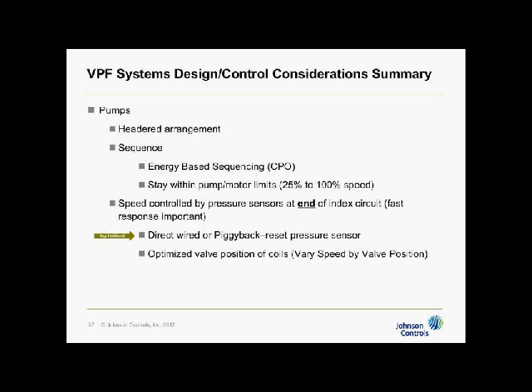Okay? Now, these pressure sensors that control variable speed drives need to be direct wired. Otherwise the variable speed drives can hunt. Don't connect a pressure sensor through the network and have it fight network traffic to control variable speed drives in the plant. They need to be direct wired. Now that can be a problem locating at the end of the circuit when you're clear across a parking lot to another building. So there are ways in which you can locate a pressure sensor in the plant that gets reset. That one in the plant is actually controlling the variable speed drive. So you get that direct control, the fast-acting control, so you don't hunt, but it is controlled through the network by the pressure sensors at the end. Now it'll work. It's called piggybacking. So the pressure sensors at the end are constantly resetting the pressure in the plant that controls the variable speed drives.